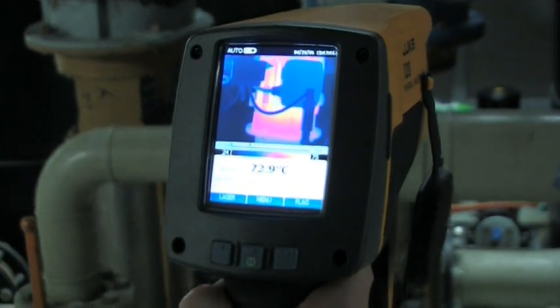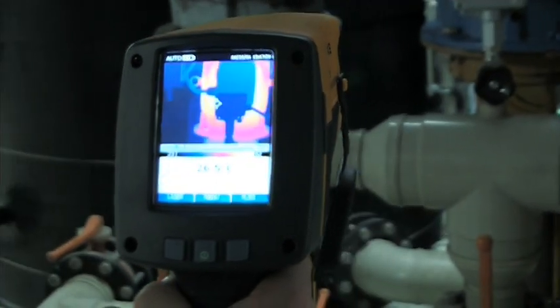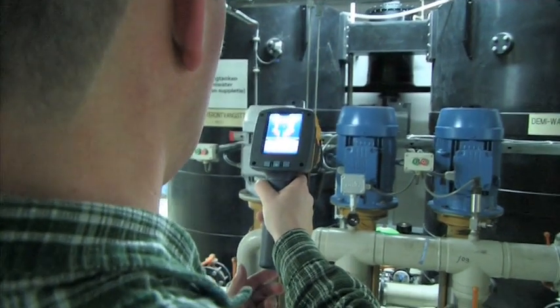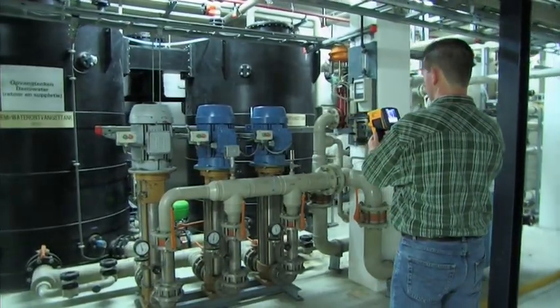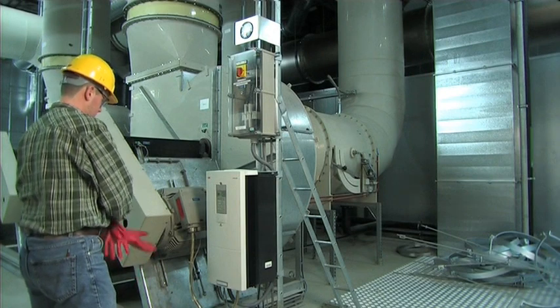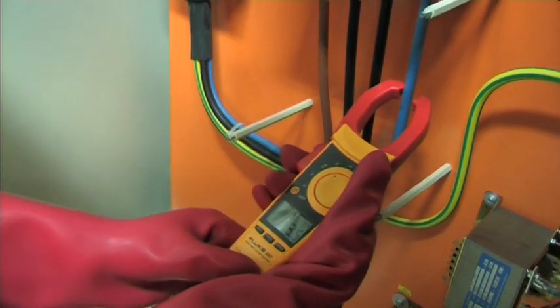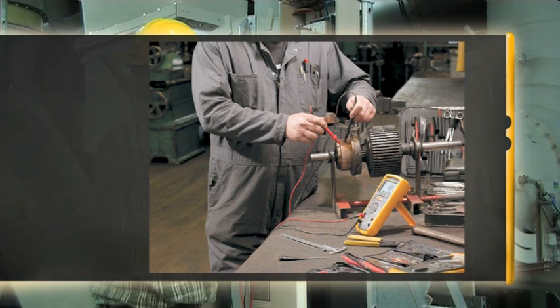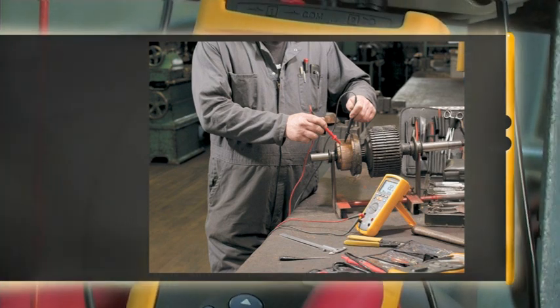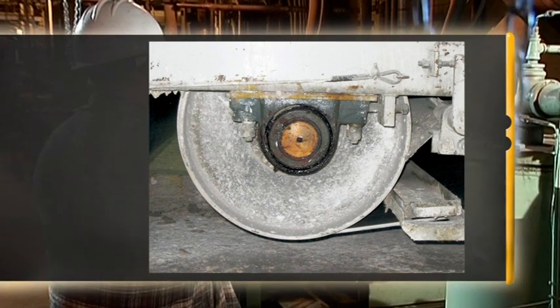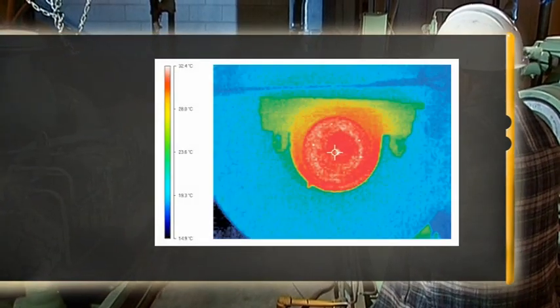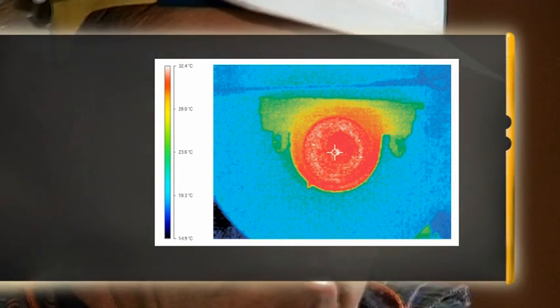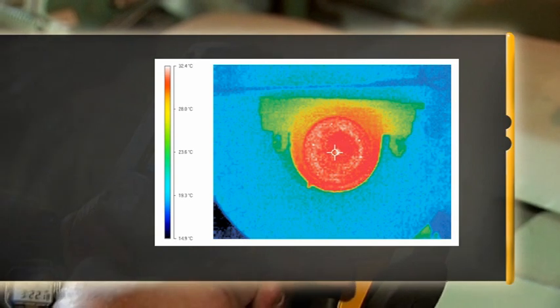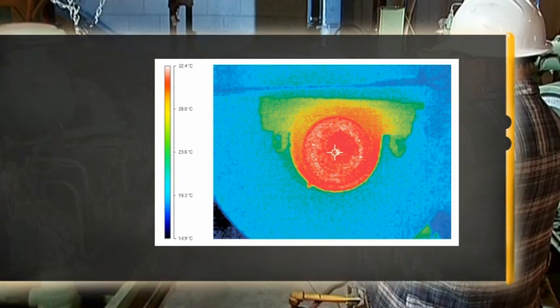A thermal imager quickly checks the operating condition and finds possible hotspots. Problem solving may be as easy as cleaning the air intake grills. For more complex problems, especially those related to the power, it's advisable to use additional measurement tools like a current clamp. The condition of the motor windings is easily checked with an insulation tester. Insulation failures should be repaired as soon as possible. An overheated bearing is easily seen using a thermal imager. Misalignment or bad lubrication might be the cause for this bearing overheating, meaning it is likely to fail if the problem is not rectified.